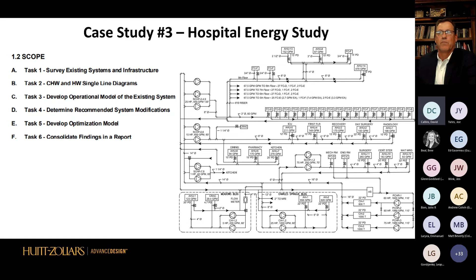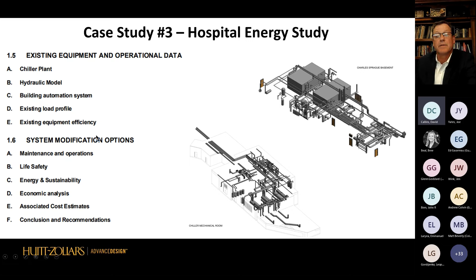So we made our operational model, and in the next slides, we went to every mechanical room. Now what's nice is that when we are looking at the piping systems, the energy just to deliver air and water through a building is much more than it takes to actually produce it through a boiler and chiller. That's why we're looking at the piping system so much. And from that, we can start looking at the load profiles, and then we can start seeing the performance of the building.